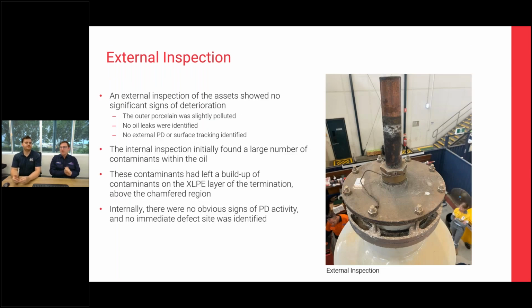So the external inspection, as Thomas mentioned, we were mainly looking for an internal evolution of the fault, so we didn't expect to see a lot on the external of the cable termination. The outer porcelain was slightly polluted, as you will get from assets that are outdoors. No signs of oil leaks were noted, and no external tracking or heating localized on the cable termination. The internal inspection found a large number of contaminants, so sediment in the oil, which we'll discuss a little bit later in the presentation, and sediment built up on the XLPE. But as for PD activity outside the termination, nothing was noted other than general effects of corona and pollution.